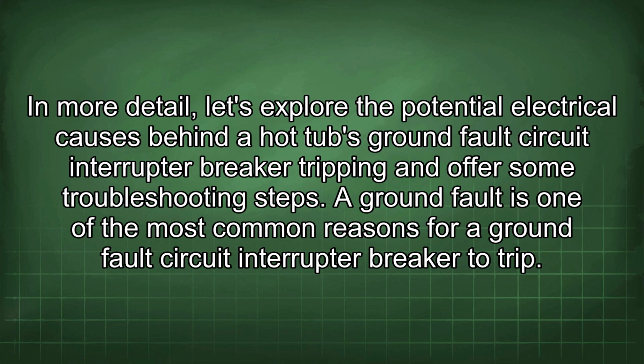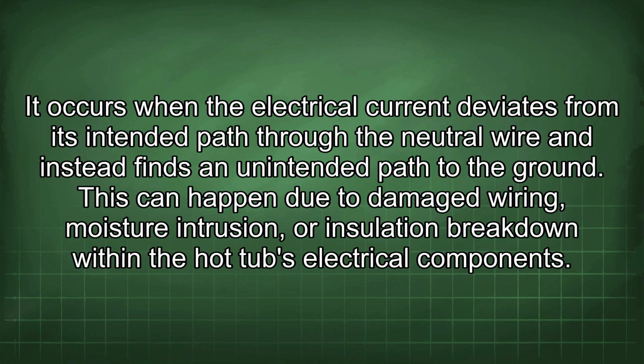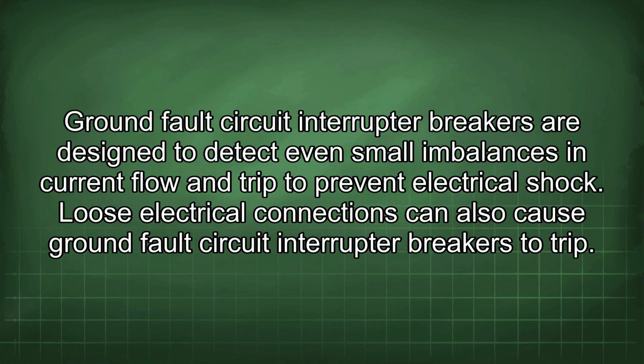A ground fault is one of the most common reasons for a ground fault circuit interrupter breaker to trip. It occurs when the electrical current deviates from its intended path through the neutral wire and instead finds an unintended path to the ground. This can happen due to damaged wiring, moisture intrusion, or insulation breakdown within the hot tub's electrical components. Ground fault circuit interrupter breakers are designed to detect even small imbalances in current flow and trip to prevent electrical shock.